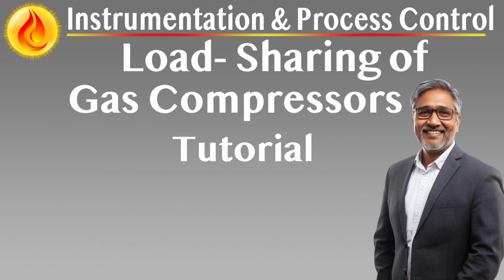Wiring and signal routing. Junction boxes at the compressor skid edge interface with all control panels. All sensors, pressure, temperature, flow, vibration, are wired using shielded segregated signal paths, analog 4-20 milliamps and digital discrete. Diagnostic-enabled HART-compatible devices are used for smart commissioning and fault identification.